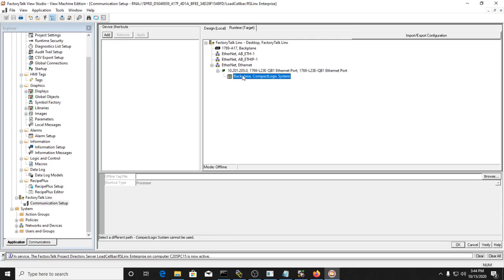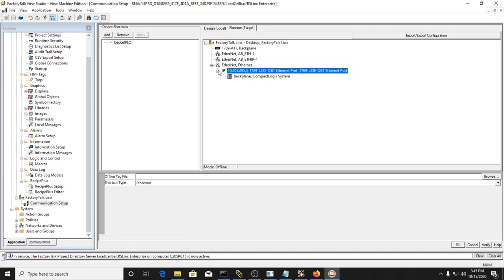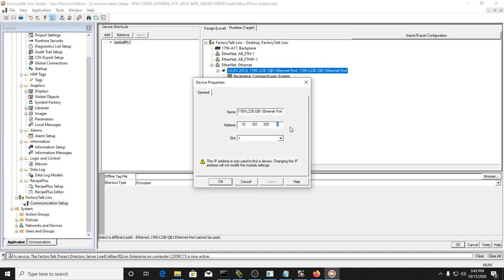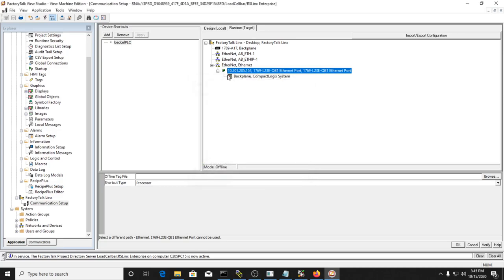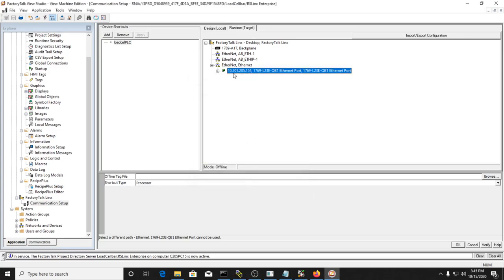After applying the settings, give it a moment to come up. I'll go to device shortcuts, add one, and name it 'Load Cell PLC.' I'm still waiting for the backplane to come up - I see now that I typed in the wrong address. I never finished typing it; 154 is the correct address, that's why it wasn't connecting. I'll type that back in and give it a chance to refresh.